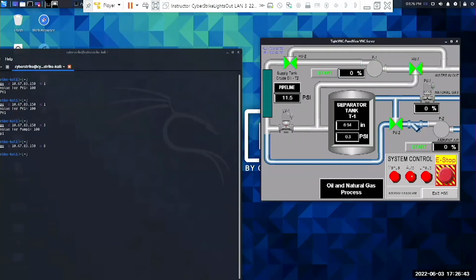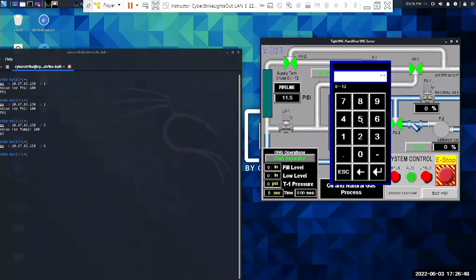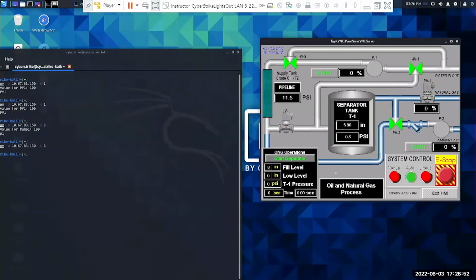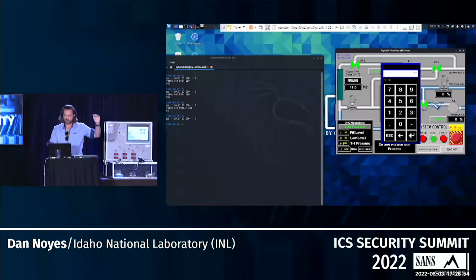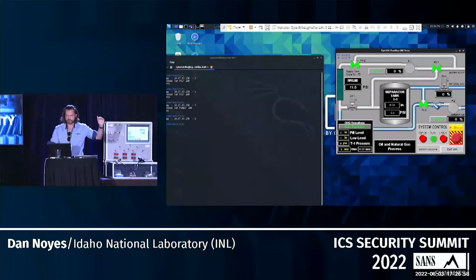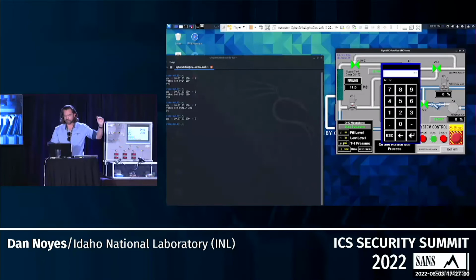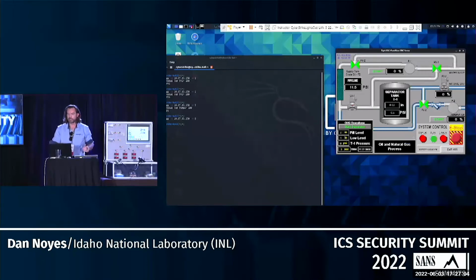In auto mode, we set parameters: when the tank gets to a certain level, that's our max and it starts draining. We've got a low level, a high level, and a pressure we want to maintain. So we set these parameters and let the system run its separation process.